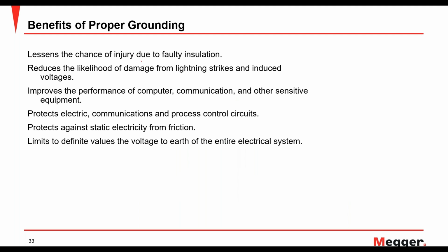What are the benefits of proper grounding? It reduces the chances of injury to the personnel. Any kind of lightning strikes can immediately be grounded. Any electrical noise that is unwanted can be grounded as well. And it protects against static electricity from friction. Let's say you have a motor that has a belt, and it can build up static electricity over a period of time, so that can be grounded as well through a good grounding system. And it limits the voltage to earth of the entire electrical system. So it's a very key component when you have a good grounding.